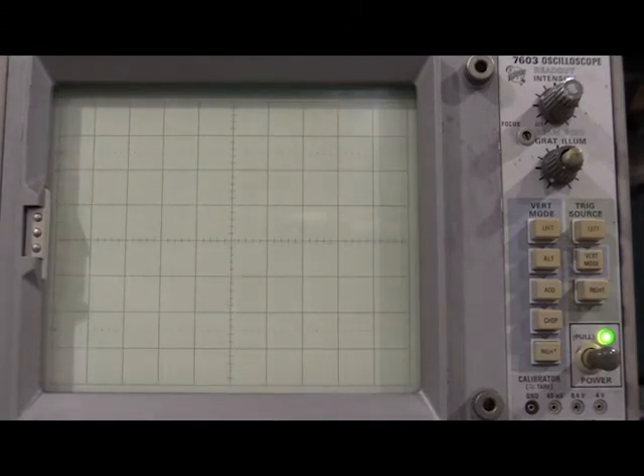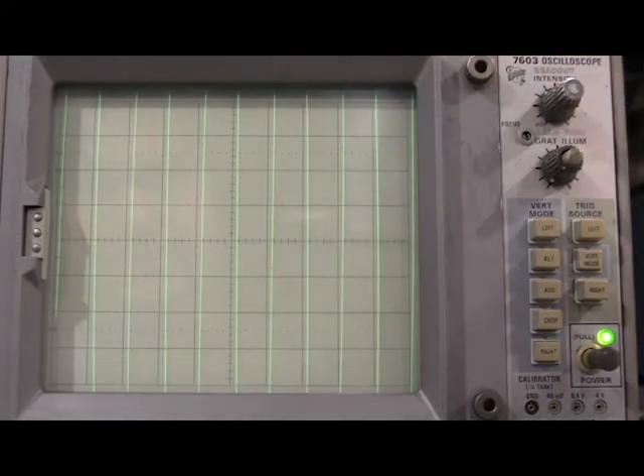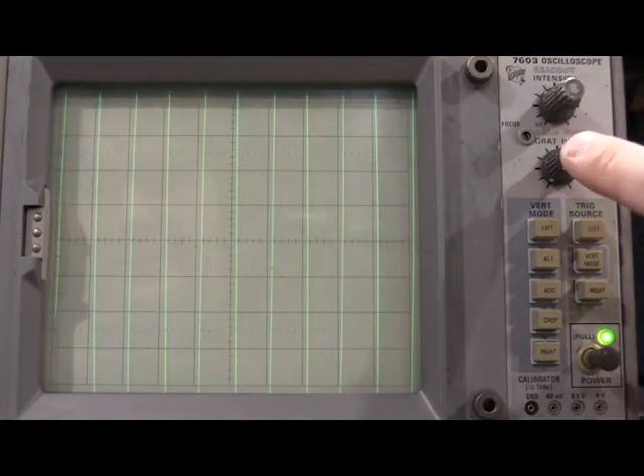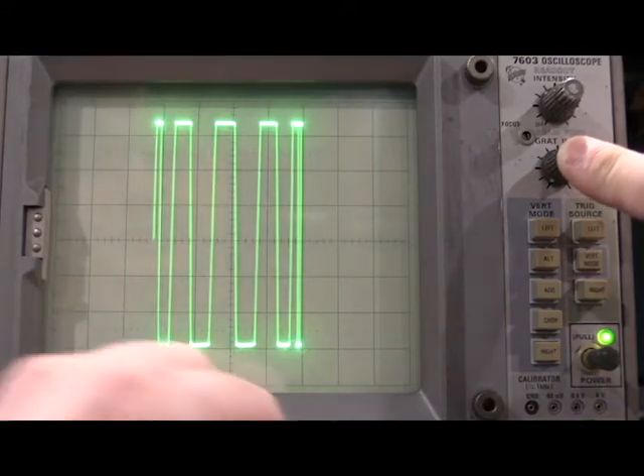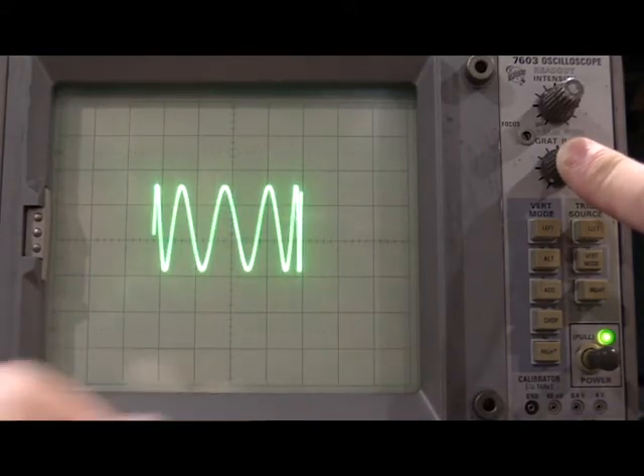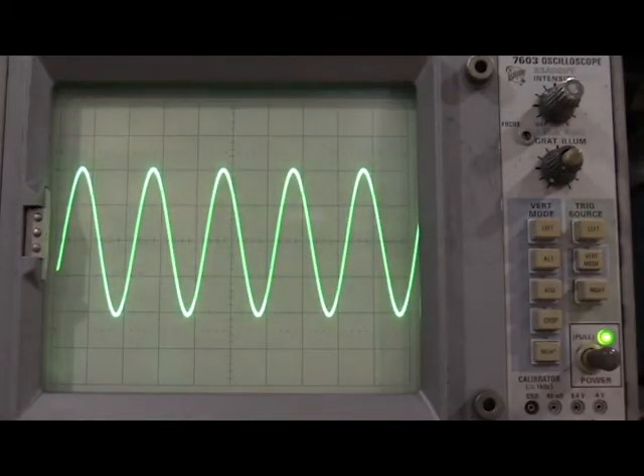So next is checking the beam finder button, that it's working correctly and compressing the display as far as it should. So I'll just brighten this up a little bit, and I'll hit the beam finder display, and that compresses into the display area, and we have our sine wave back, and I can get it back on the screen. So the beam finder is working.